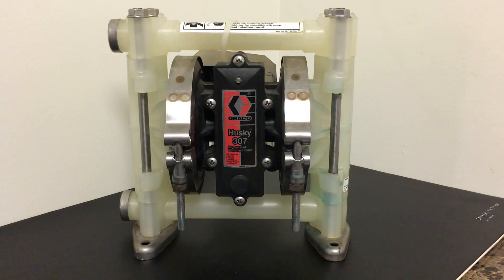How do you tell which one has the issue? You want to turn up the pressure on your pump. If it's at 40, bump it up to 50. If it's at 50, bump it up to 60. Just don't go above 80 - this pump really can't handle PSI like that. If you turn up the air pressure and you see that the pressure starts to slowly drop over time, you know that it's a diaphragm. If it's leaking, if the pump is just losing pressure, you know it has to do with a seal or a diaphragm.